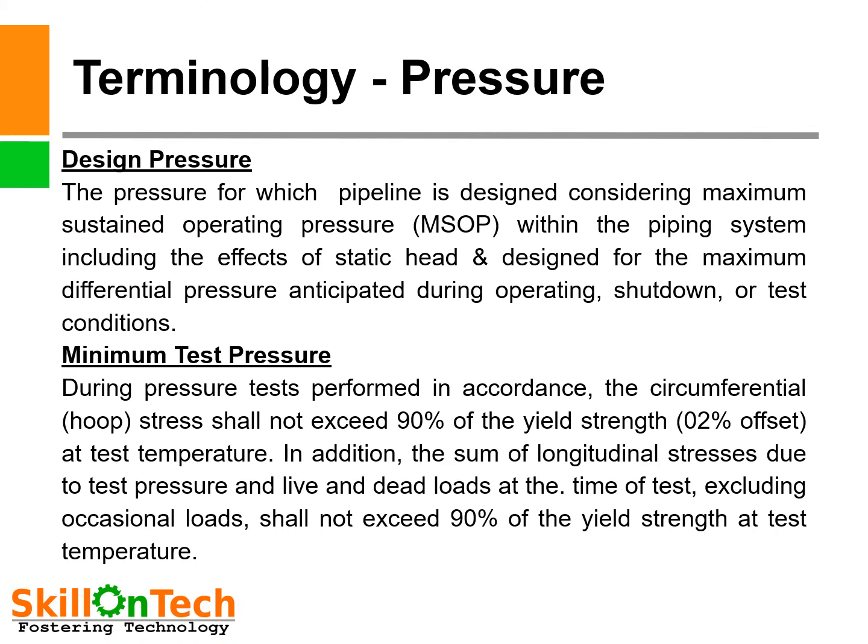What is the terminology used for hydrostatic test as per code? Design pressure is the pressure for which the pipeline is designed, considering maximum sustained operating pressure within the piping system including the effect of static head, and designed for the maximum differential pressure anticipated during operating, shutdown, or test conditions. During a pressure test, the circumferential hoop stress shall not exceed 90% of the yield strength at 2% offset at test temperature.